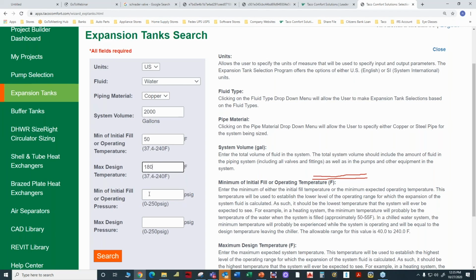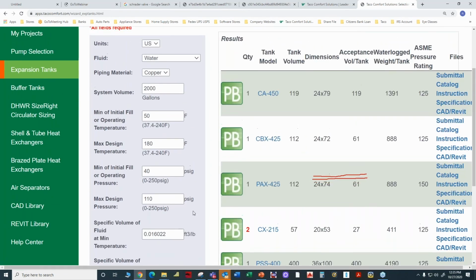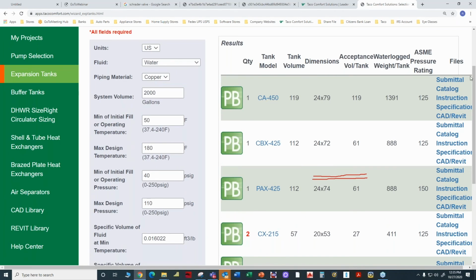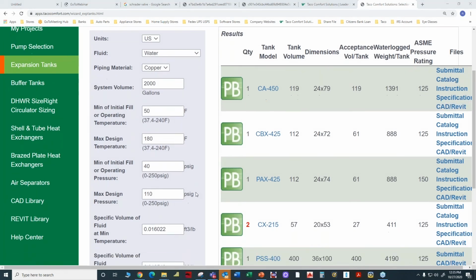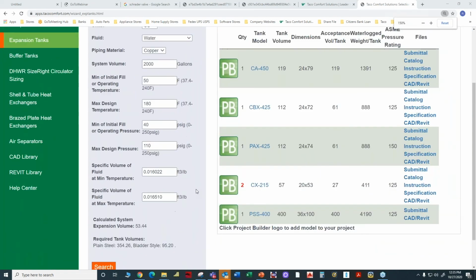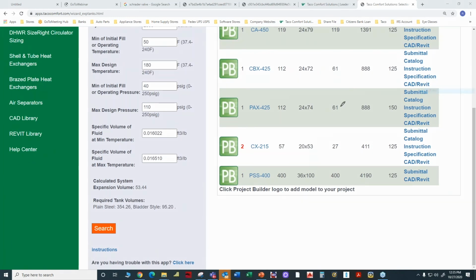Now I need to have the minimum or fill pressure at the expansion tank, and we calculated that, and we said that that was 40 pounds. And the maximum pressure we wanted at the expansion tank is 110. Now I've filled in all the data, and that's all I need for this app. And then I click on search. When I click on search, oops, let me erase this couple of little red lines here. The software has made several selections. So before I go into the actual selections, I want to point out a couple of quick things that the software has done. The software has looked up the specific volume of the fluid at the minimum and maximum temperatures. And between those two values, one there and one there, and the volume of the system, I should have scrolled down just a hair.